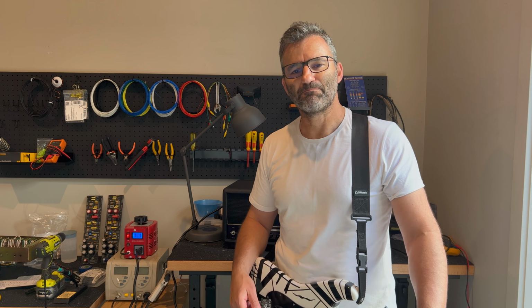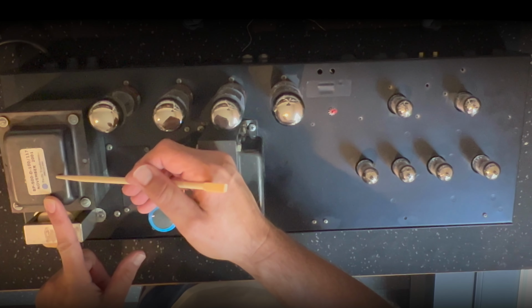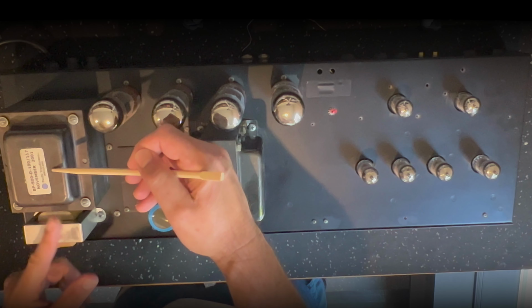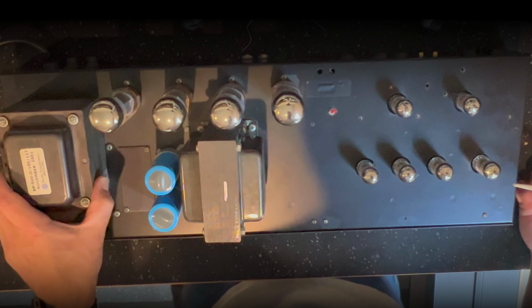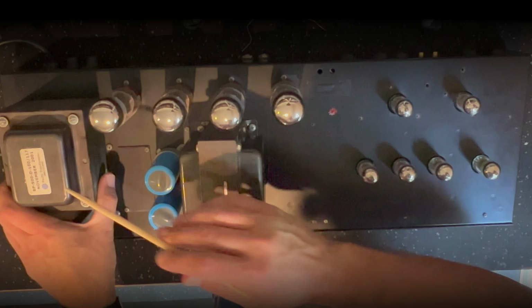Let's do that now. Alright, we've got this bad boy out of the head cab. First thing I've noticed is this power transformer, it's Pacific Transformers. I suspect this is not original, I could be wrong. But I'm going to have a look at this and see if I can find any information about this particular model, because I'm hoping this might be an international transformer. I might be able to wire this to 240 on the primary side, which would negate the need to pull this out and replace it and rewire it, which is quite a big job.